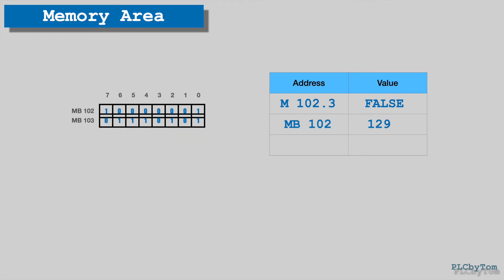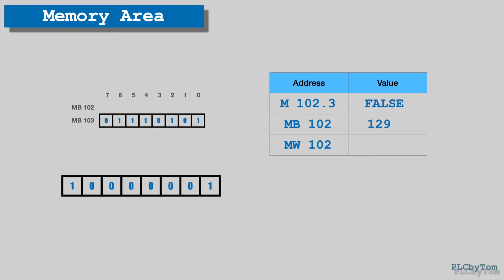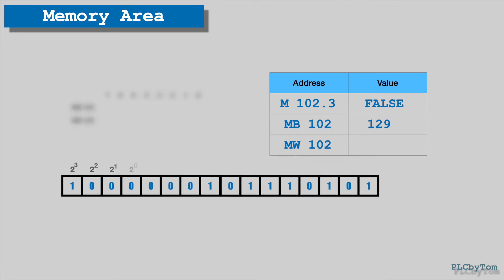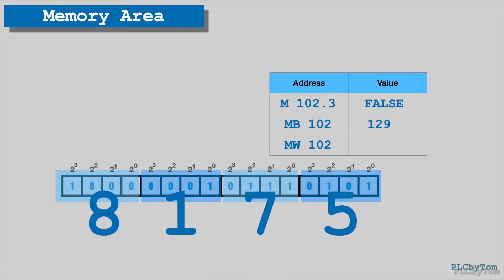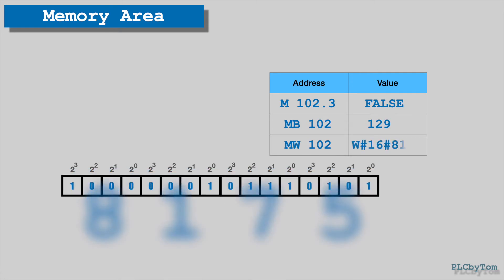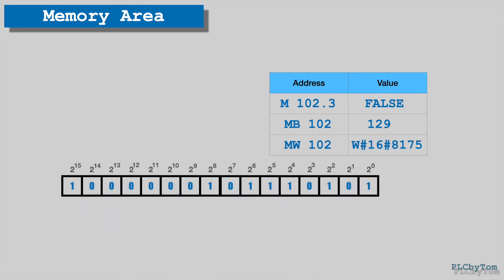To address word data, address format is MW102, and memory location of two bytes 102 and 103 is taken and concatenated into a word, where byte 103 is less weight than byte 102 in word. Then in hexadecimal representation we get 8175 hexadecimal numbers or in decimal representation it is 33141.